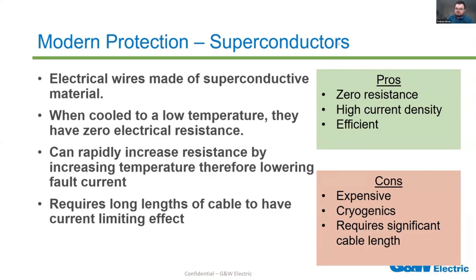So once again, those pros: zero resistance. That means near zero losses. That can be very valuable, especially in long distance transmission lines. You have very high current density, meaning you can move a very large amount of current through a small cable. And ultimately, these are very efficient devices as a result. You can install these on poles that are much smaller than you would argue that you need otherwise.